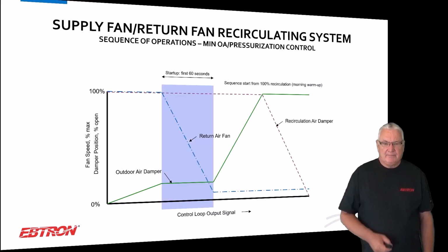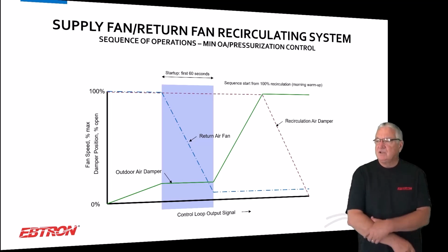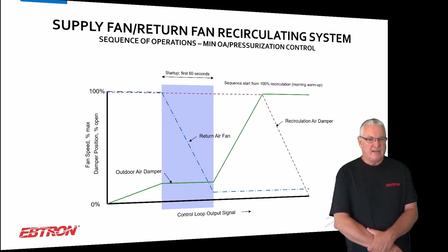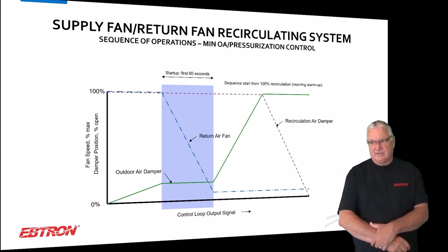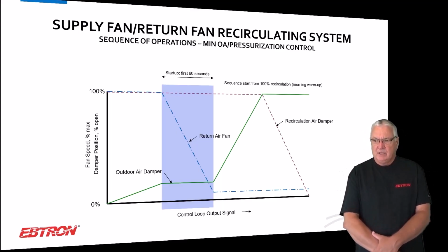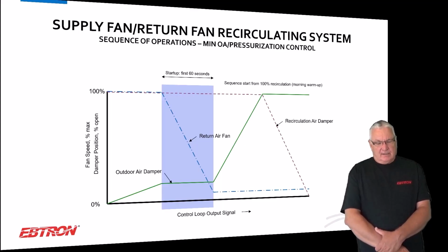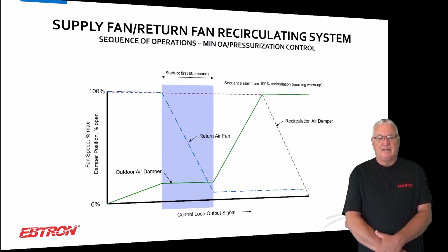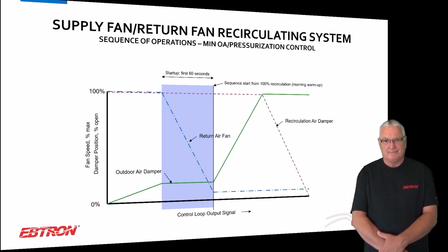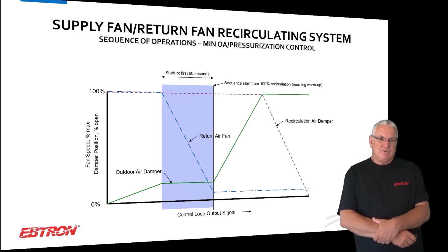And so we have a startup sequence. One of the problems with return fans, and I like return fan systems a lot, actually, is the potential for them, if they're not set up right, to blow air out the intake when you start your sequence. And so what we like to do is start with the return air fan at its lowest speed, which is at the right side of that blue space on the screen.